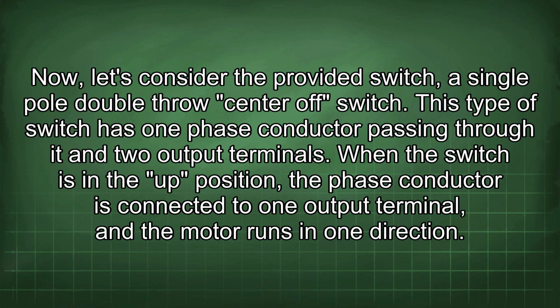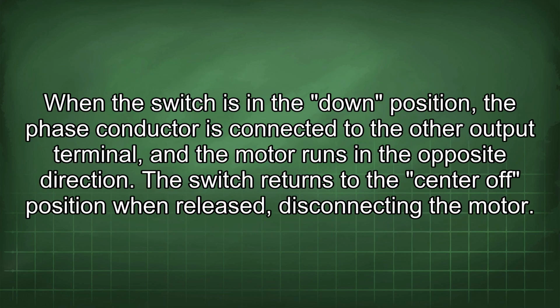When the switch is in the up position, the phase conductor is connected to one output terminal and the motor runs in one direction. When the switch is in the down position, the phase conductor is connected to the other output terminal and the motor runs in the opposite direction. The switch returns to the center off position when released, disconnecting the motor.